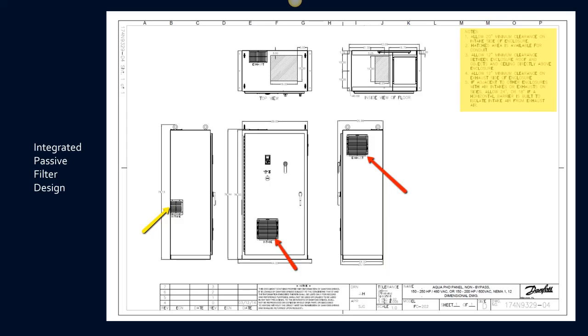And there's a disadvantage to this. You're going to see exhaust and intake vents, and those require what? Clearance. So in addition to that, this setup is 39 inches wide. And so if we're paying $300 a square foot for a block building, or $150 for an e-house, this gets quite expensive. So here's a better way to do it.